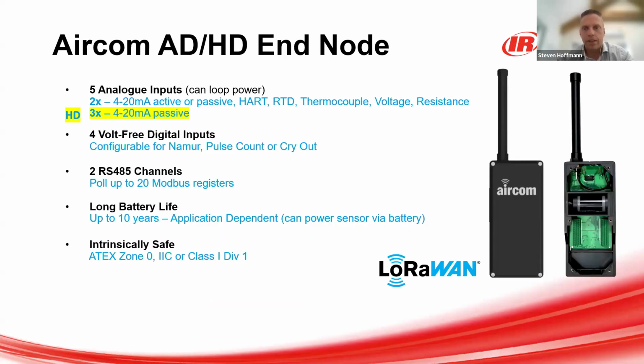So just to highlight our Aircom AD/HD end node, you can see the difference with the HD is we add 3 additional analog inputs on it. So with the AirCom end nodes, you can have up to 5 analog inputs. We can loop power those instruments, take the readings and send them back. 2 of those are highly configurable for either active, passive, HART, RTD, thermocouple, voltage, or resistance. The other 3 on the HD are just going to be passive only.